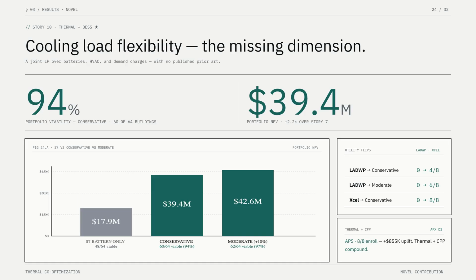LADWP conservatively flips from 0 of 8 to 4 of 8, and moderately 6 of 8. Xcel flips from 0 of 8 to 8 of 8. The cooling shift bypasses that rider barrier, and when we layer CPP enrollment on top of thermal, APS gains another 855,000. To my knowledge, no published research combines BESS, cooling load scheduling, and demand charge optimization in a single LP.